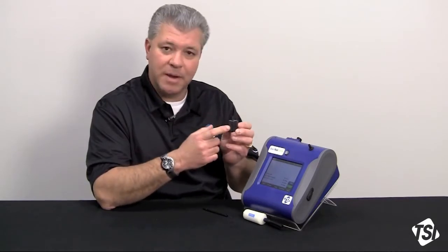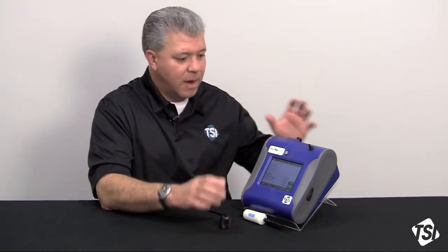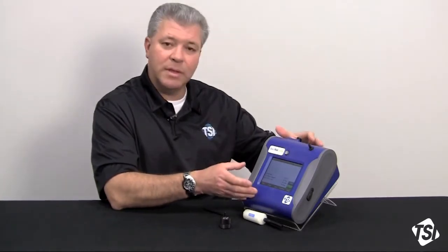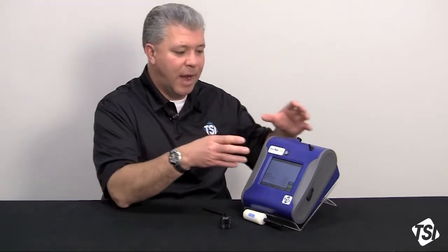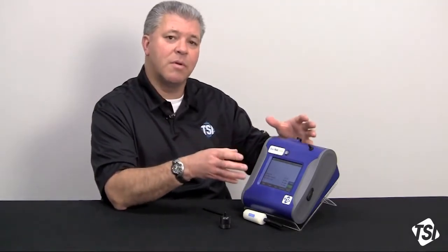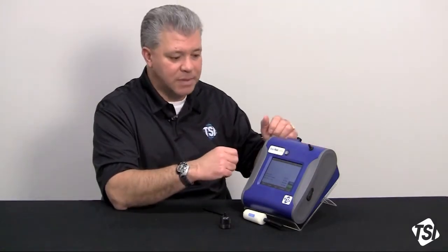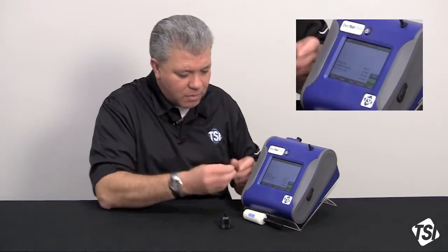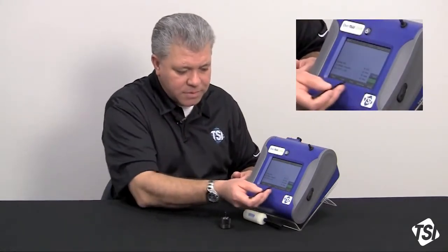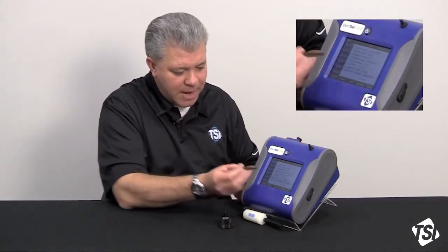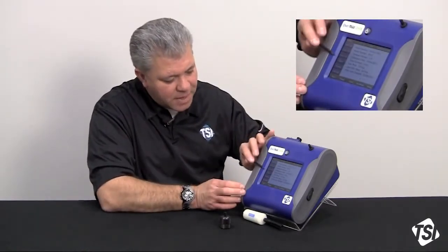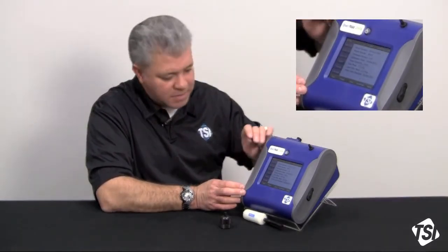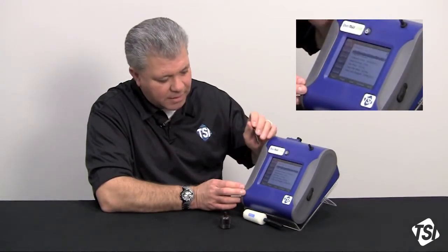And we have a PM 2.5 impactor that has been greased up already. It's ready to go. And now, let's assume we're doing this in the work area or the ambient area that we're going to do our sampling. And we're concerned that the aerosol we're going to measure may be different in response than the Arizona road dust, the A1 test dust. So, we're going to utilize the lower setup screen here. I'm going to press the setup tab. And across the left side of the instrument, we're going to see another row of icons come up. And we're going to go to the user cal icon.